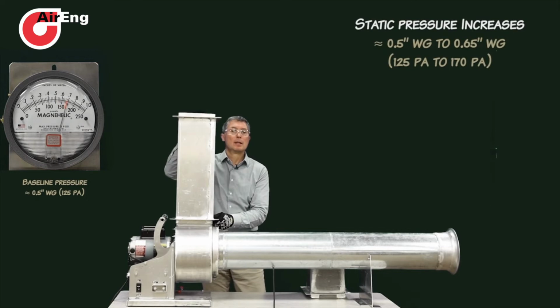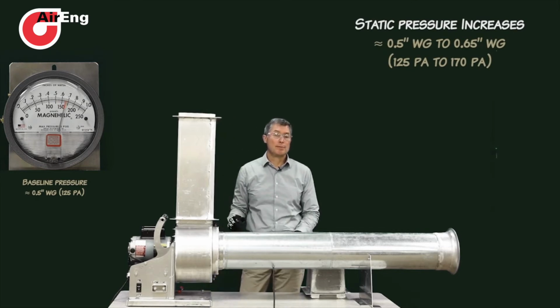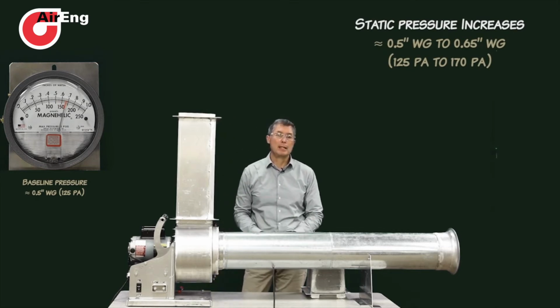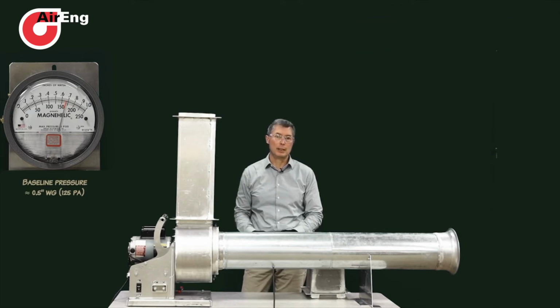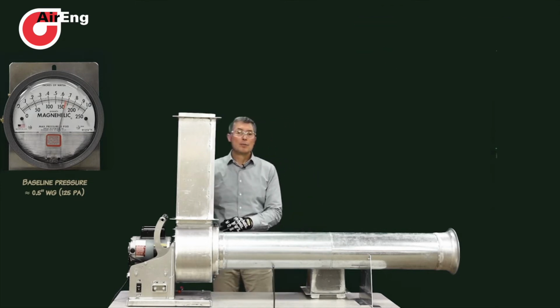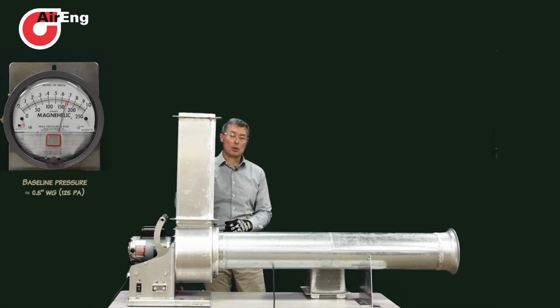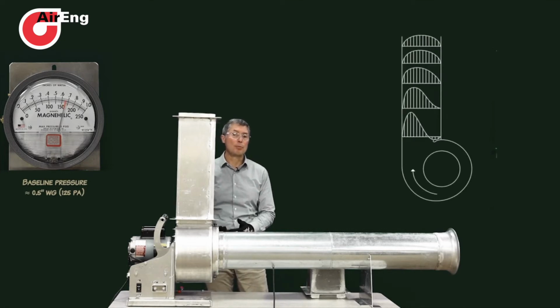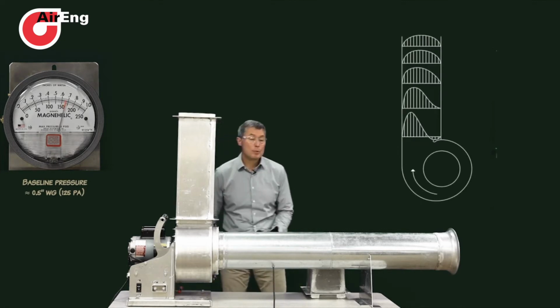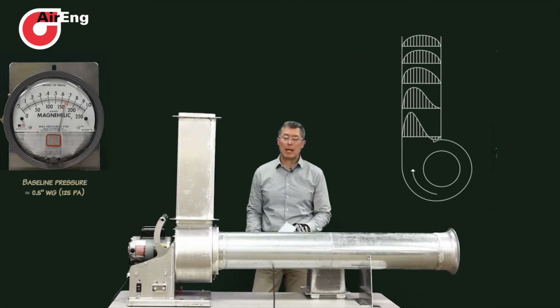Put it on the outlet, and we notice that the velocity pressure measured by the magnehelic has gone up pretty substantially. And that's because we have static pressure regain in this piece of ductwork, and we're allowing the velocity profile to even out. What do I mean by an evened out velocity profile?